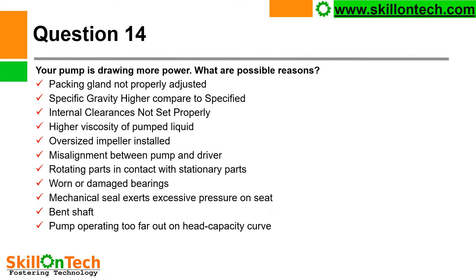Your pump is drawing more power — what are the possible reasons? If your pump is drawing more power, energy consumption is high and the pump is running at very high cost. Gland packing not properly adjusted — if it is more tightened, it must be appropriately tight, so there should not be excessive leakage from the gland packing and the gland packing should not get hot. Specific gravity higher than that of the specified liquid. Internal clearances not set properly. Higher viscosity of pumped liquid.